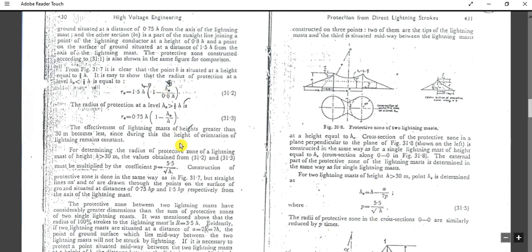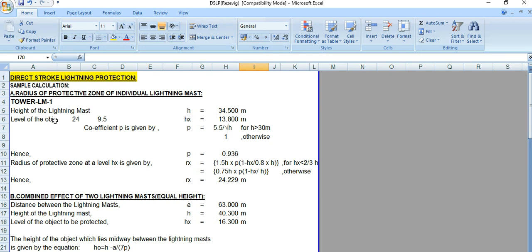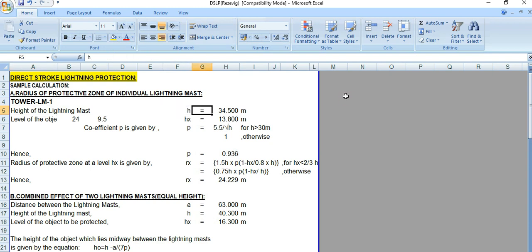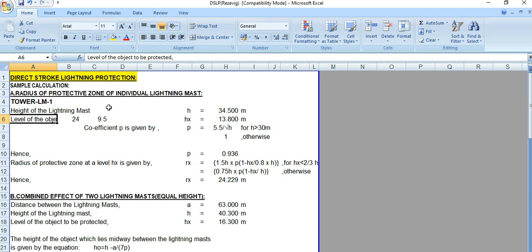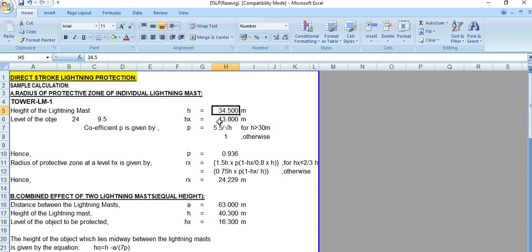For the single mast direct stroke lightning protection, let's go to the Excel spreadsheet. Suppose the tower name is LM1. The height of the lightning mast, small h, equals 34.5 meters. The level of the object to be protected, denoted hx, is 13.8 meters. So we have two inputs: the lightning mast height and the height of the object to be protected.